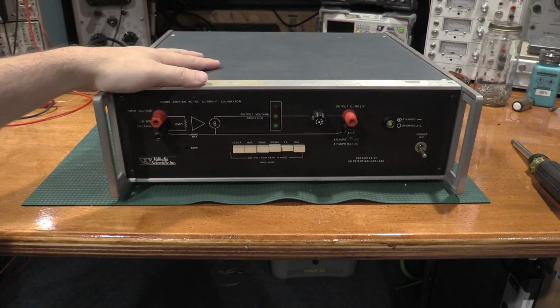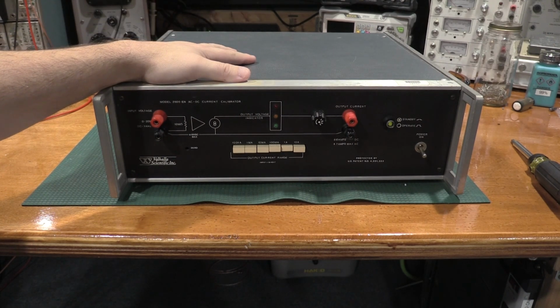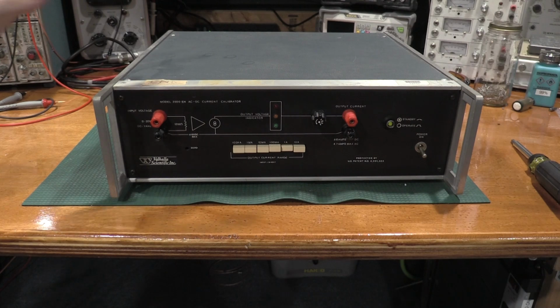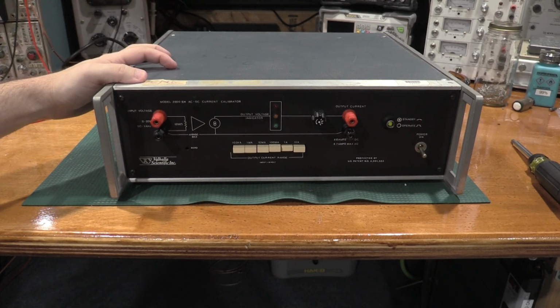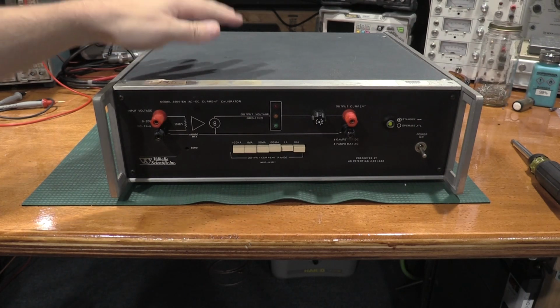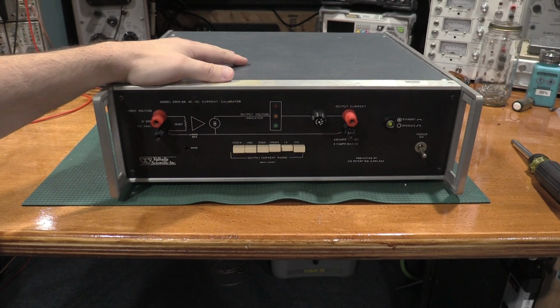Now, ideally this is an ideal current source. An ideal current source would be able to reach an infinite voltage, similar to the SMU, up to its output. This tops out at 10 volts. So it's really designed to drive shunts, things like that, with known currents in AC and DC, also of both polarities. You can have negative current, i.e. a negative supply, pushing through a load. This does not create power. This is not an infinite energy machine at all. This burns a lot of watts, actually. It's forced air cooled, but it can produce current in a negative polarity.